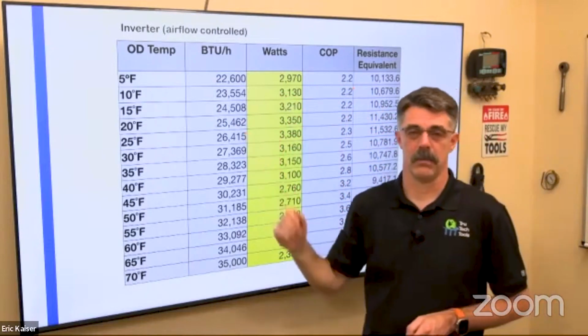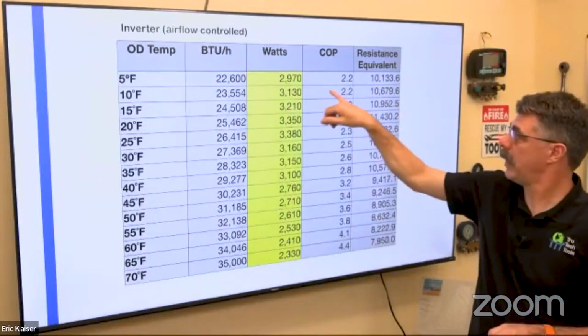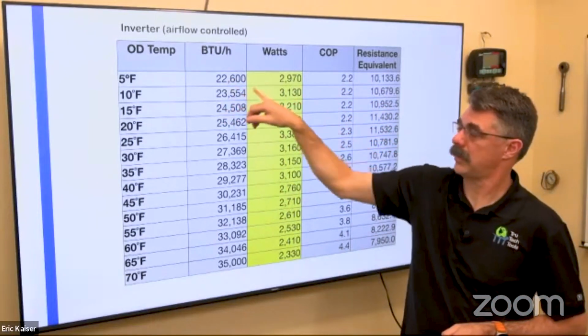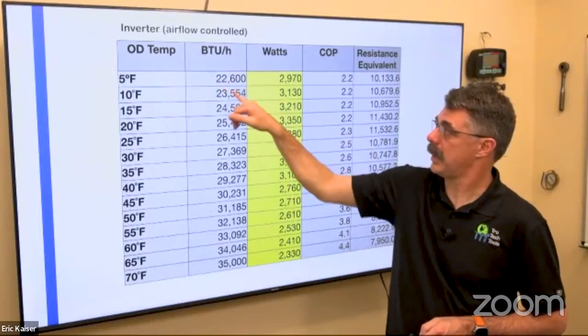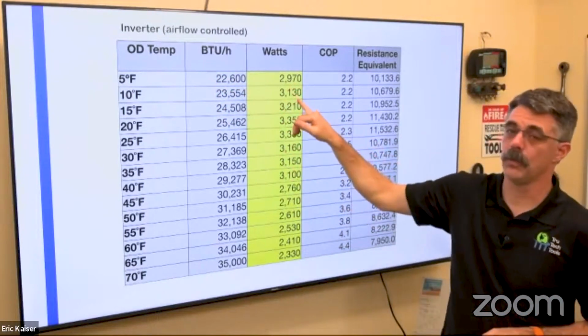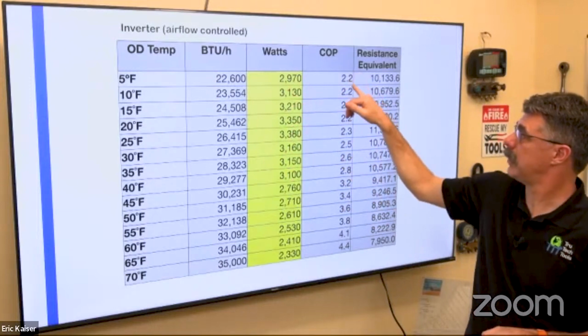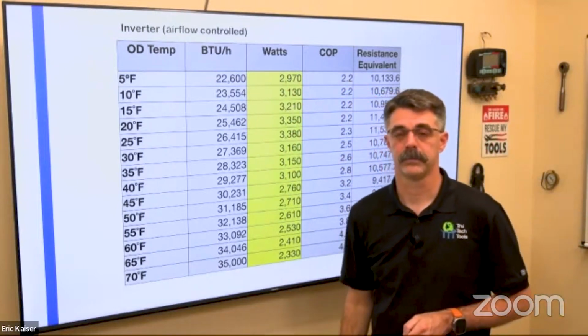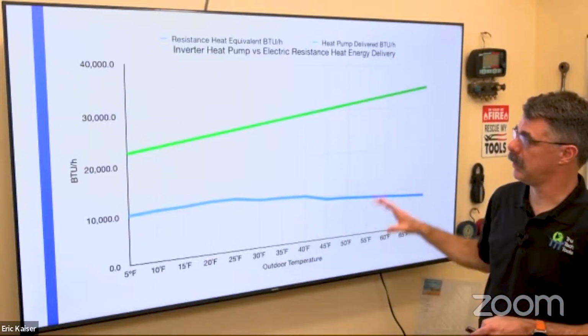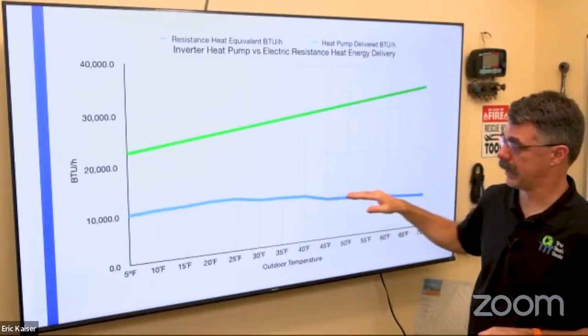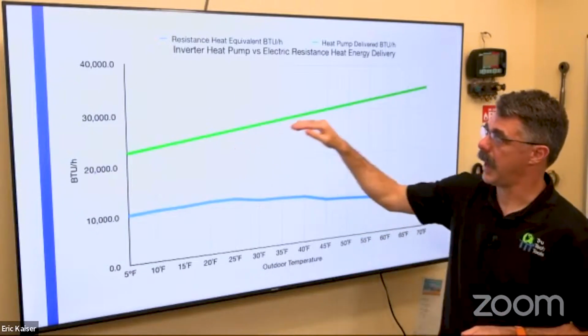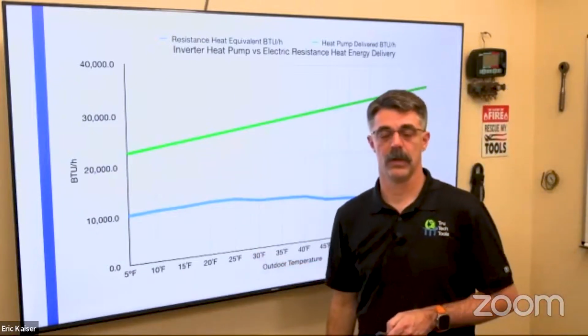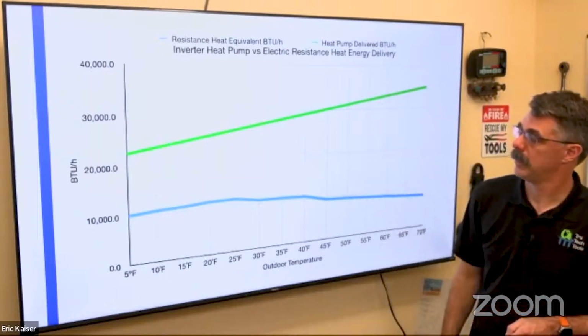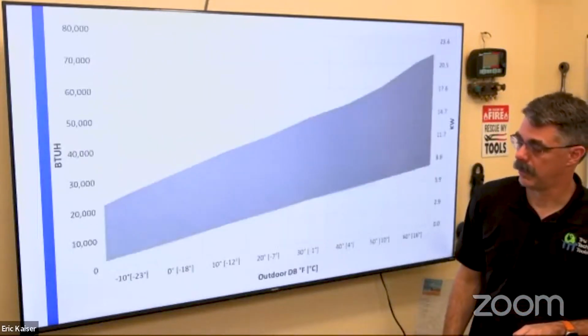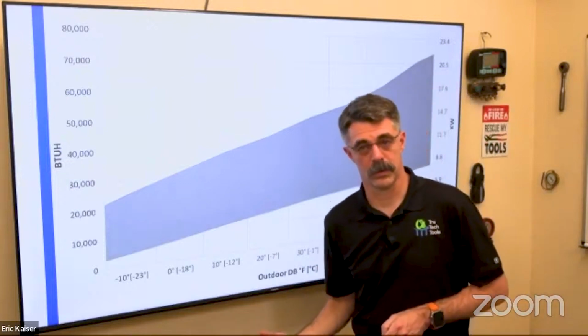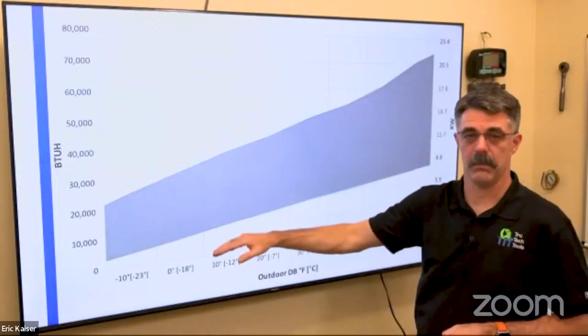So I plotted them the same, right? They'll run lower than that. But all the way down here at 5 degrees, you see it's the same nominal tonnage unit, but I'm making more BTUs per hour. I am using a few more watts than that single stage was, but I still have good COP out of it. All right. And this is the performance slope on that, again comparing the resistance electric heat and the performance delivered BTUs of that inverter heat pump.